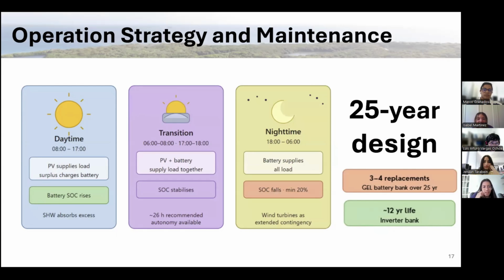The system operates across three distinct modes. During daylight hours, the PV array supplies the community load directly and simultaneously charges the battery bank. During transition periods around sunset and sunrise, generation and storage share the load; during nighttime hours, the battery bank supplies the entire community demand. To preserve battery lifespan, depth of discharge is recommended not to exceed 30%, with a minimum set at 20%, yielding a practical operational autonomy of approximately 26 hours.